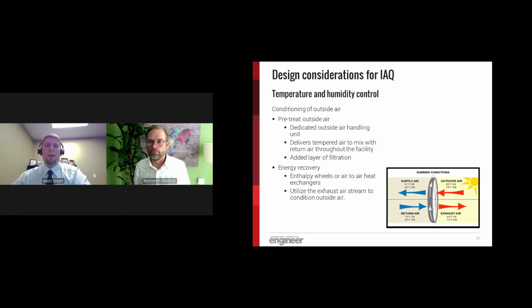So we've discussed a lot about filtration and ventilation to properly remove contaminants from the airstream. However, equally as important is temperature and humidity control. Obviously, the primary source of high humidity in a building is the ventilation air. This is especially true in an environment where ventilation rates may be high, requiring more ventilation air.